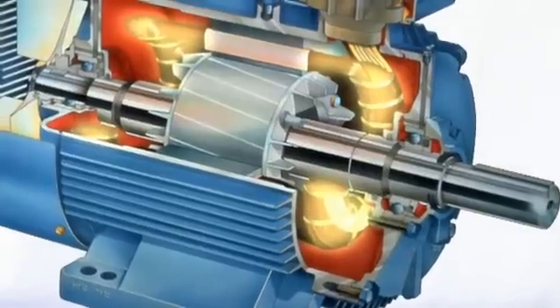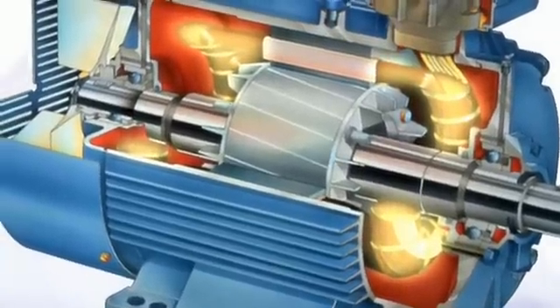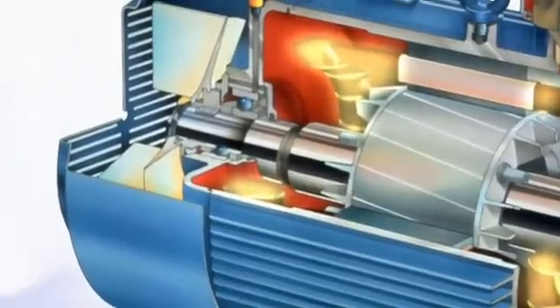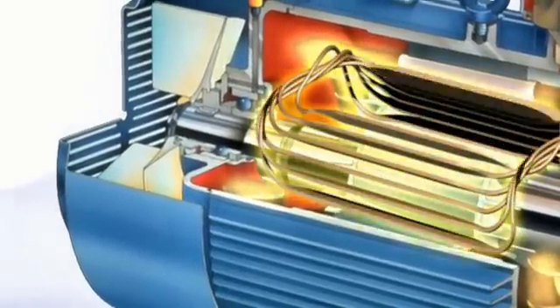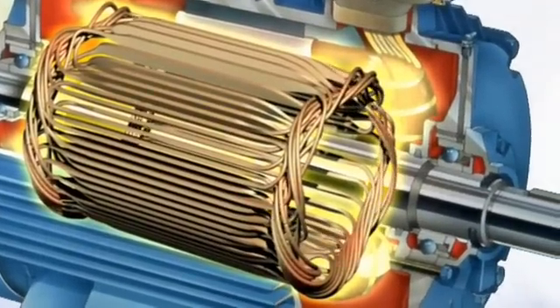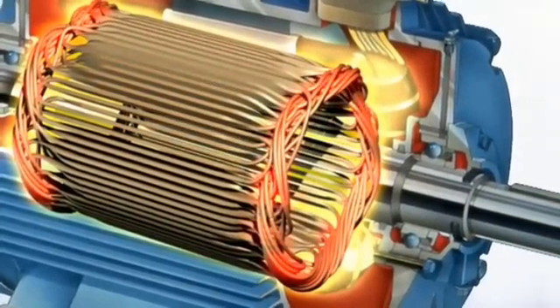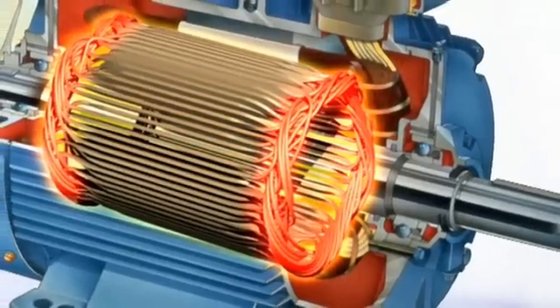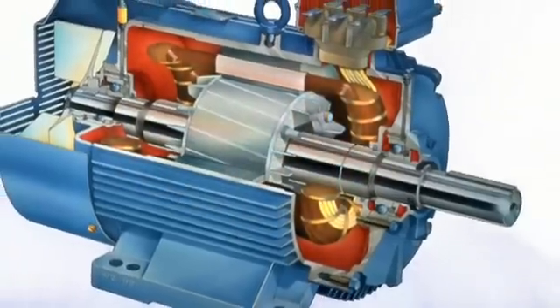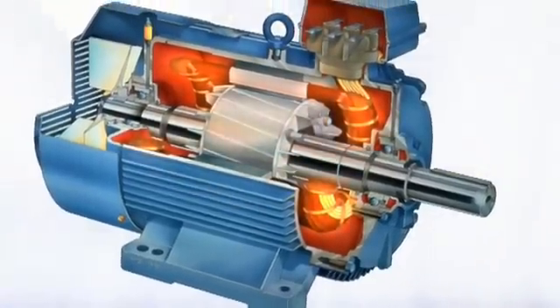The long stator with overlapping windings at each end not only restricts application of the induction motor but also introduces a significant failure risk resulting from overlapping coils which are subject to hot spots and insulation breakdown. Excessive currents are required to initially magnetize the rotor and start rotation. Frequent starts can rapidly overheat the motor.